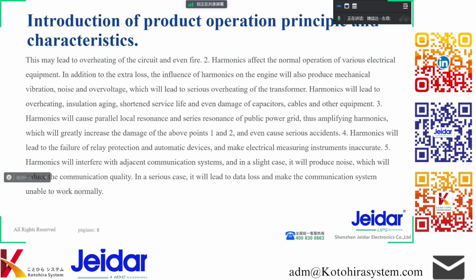Harmonics will lead to the failure of relay protection and automatic devices, and make electrical measuring instruments inaccurate. Harmonics will interfere with adjacent communication systems, and in a slight case, it will produce noise, which will reduce the communication quality. In a serious case, it will lead to data loss and make the communication system unable to work normally.